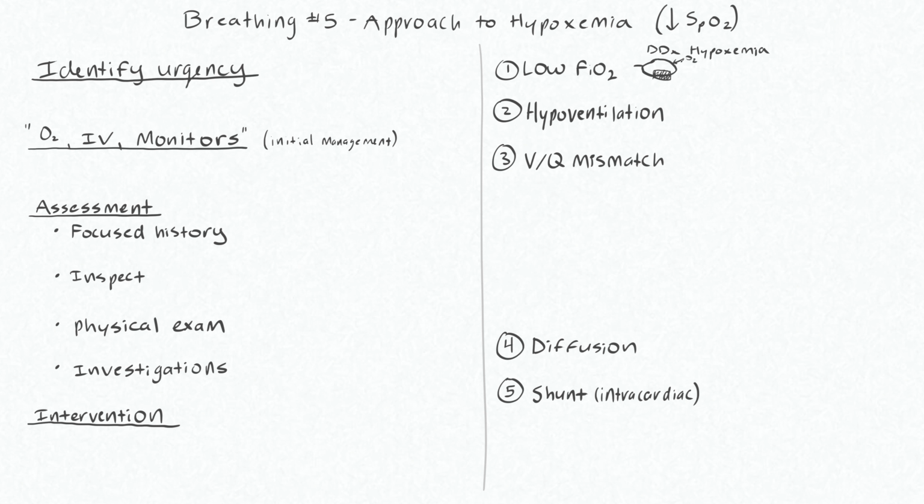So in this case, you could be delivering low FiO2, although you should get some kind of alarm warning you that this is the case in this scenario. And of course, if there is some issue with the O2 delivery mechanisms of the anesthesia machine, you could also deliver a hypoxic mixture. Otherwise, this is very unlikely.